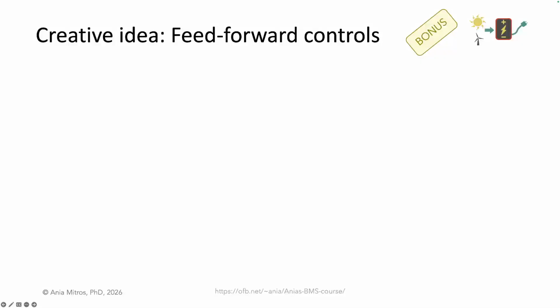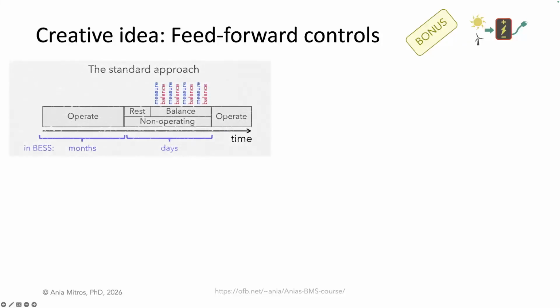In this bonus slide, I'll tell you about a controls idea that I think is worth considering, in particular for batteries where a non-operating state is infrequent. For example, a BESS with the standard approach might operate for several months. Because it's mostly operating in the middle of the SOC range, and because it's built with LFP cells, normal operation doesn't provide opportunities to assess the state of imbalance. From time to time, the battery pack is taken offline, discharged and rested, such that the state of imbalance can be accurately assessed. The pack then spends some hours or days balancing until it is brought into balance. Only then does it return to regular operation.